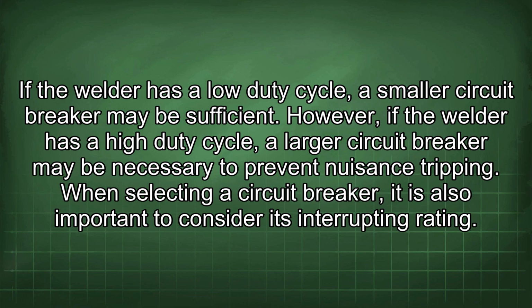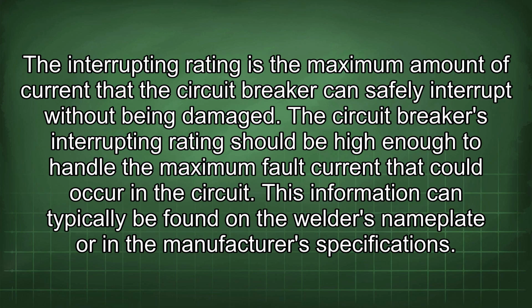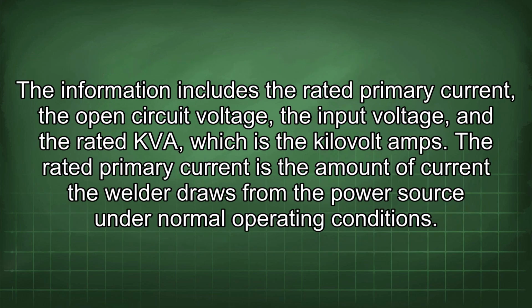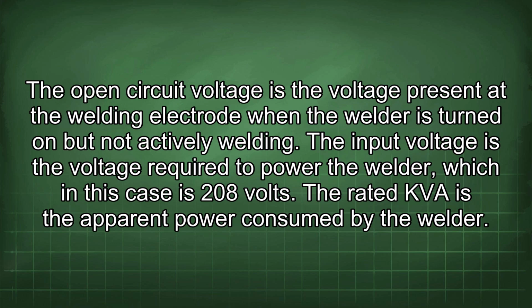When selecting a circuit breaker, it is also important to consider its interrupting rating. The interrupting rating is the maximum amount of current that the circuit breaker can safely interrupt without being damaged. The circuit breaker's interrupting rating should be high enough to handle the maximum fault current that could occur in the circuit. This information can typically be found on the welder's nameplate or in the manufacturer's specifications. The information includes the rated primary current, the open circuit voltage, the input voltage, and the rated kVA, which is the kilovolt amps. The rated primary current is the amount of current the welder draws from the power source under normal operating conditions. The open circuit voltage is the voltage present at the welding electrode when the welder is turned on but not actively welding.